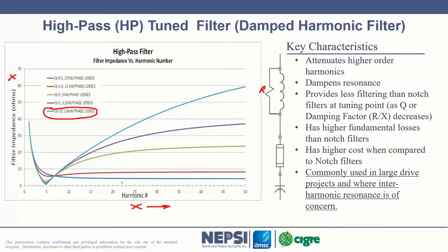The other thing to note here is as we go up in frequency, we offer lower impedance to the system. So these filters, as you can see, they're high pass filters because they're passing high frequency currents into the filter. It's offering a path around the reactor through the capacitor. At high frequency, if you think about it, X of L is going to be high, X of C is going to be low, and the value of R is going to be constant with frequency. Technically it's not, but let's just say for simplicity it is. Current will want to flow through the resistor because X of L got very large, so we get this characteristic shape that you see here.